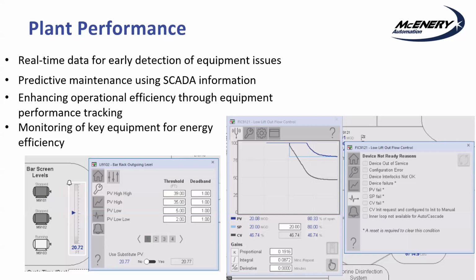A lot of that can be set up just from simple faceplates on your system - put in set points, and time frames for how long it needs to be in an alarm condition before we really need to care about it.